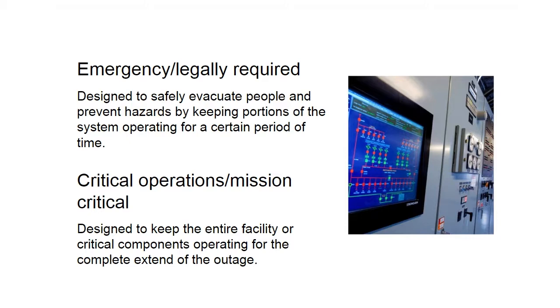But depending on the facility type, whether it's a hospital, healthcare facility, or mission critical COPS type facility, you have your separation of load types, so your emergency and legally required loads. Those, again, are really designed to safely evacuate people and prevent hazards, to get people out of the building in the case of normal utility loss of power. In the healthcare arena, obviously you want to continue to maintain patient care functionality and ensure the patient will continue to be supported with the equipment that is there at the bedside or in the procedure room where the patient might be.